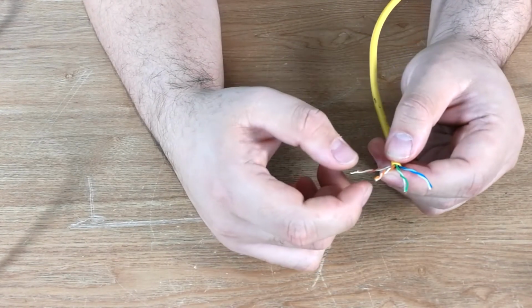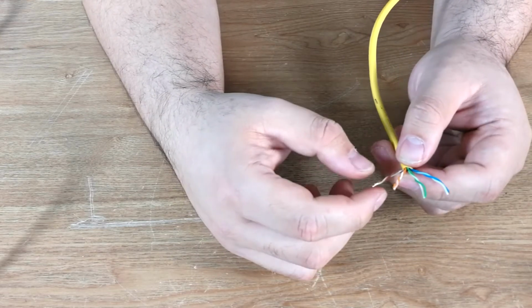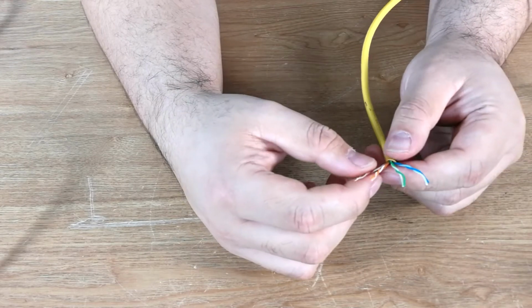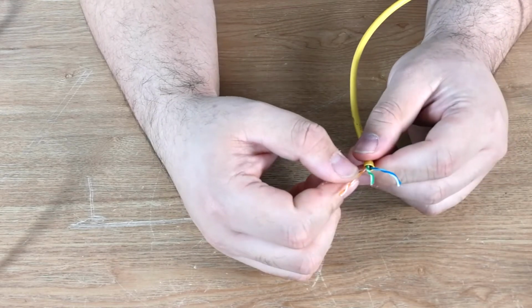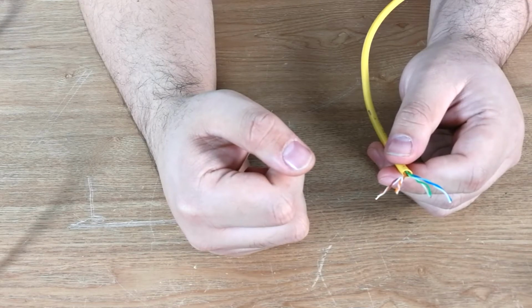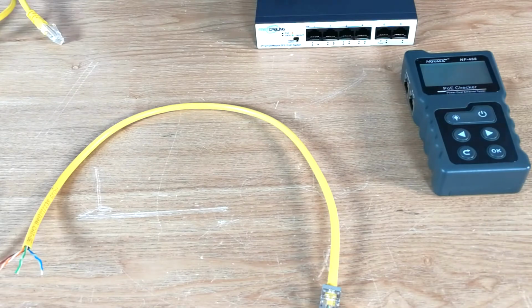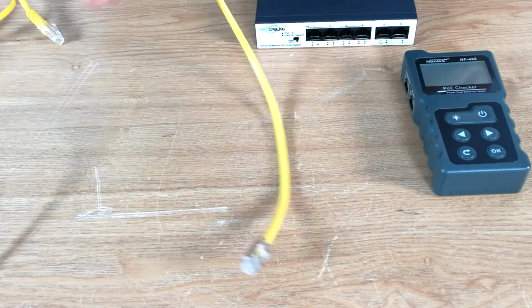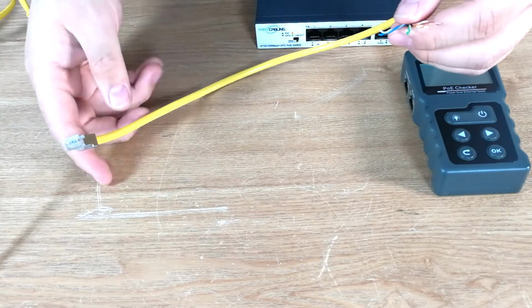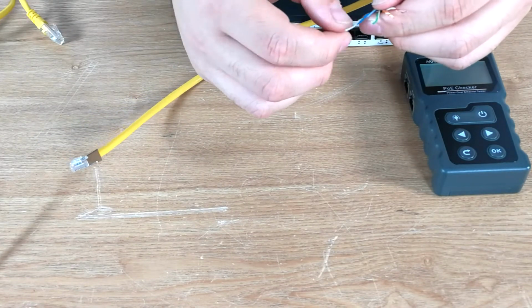So when we use the method we learned from the video, we should make sure that we have the PSE that will occupy 2 pairs of twisted wire for power and data. So here are some methods we can use to see if our 4 pairs of wire are all occupied or only 2 of them are occupied.